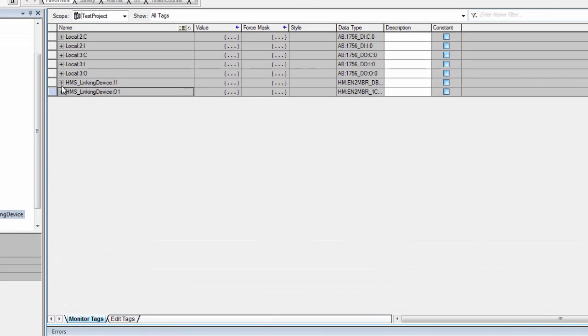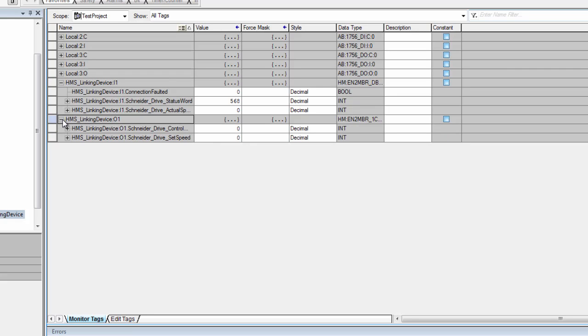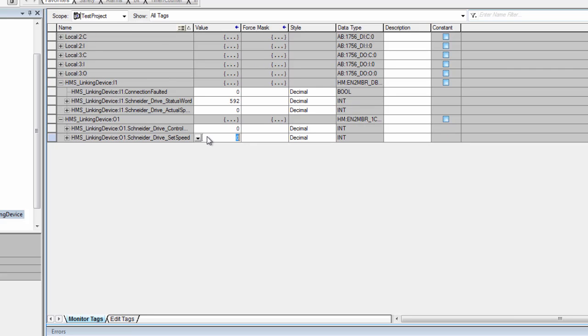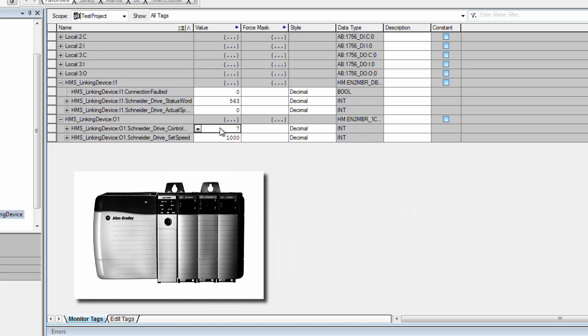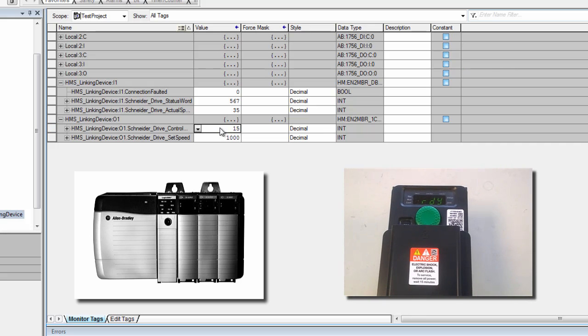When the download is finished, I click on Monitor Tags and I can now test the connection by typing in a couple of values for the drive into Rockwell Logix Designer. And I can see that the Rockwell ControlLogix PLC is now communicating with the Schneider Drive.